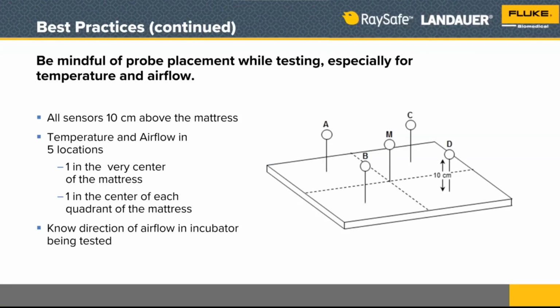Now, not only that, but your temperature sensor needs to be not sitting on the mattress, but it needs to be 10 centimeters above the mattress. And that's because the baby and the central core, the vital organs of the baby, are not on the mattress. They're above the mattress by about 10 centimeters. So we really want to control the temperature at the baby's core. And that's really what we're trying to do here.